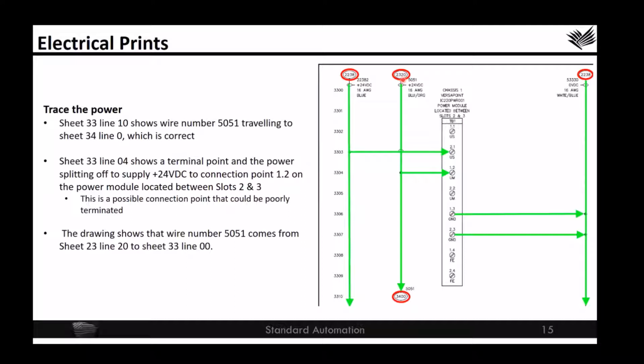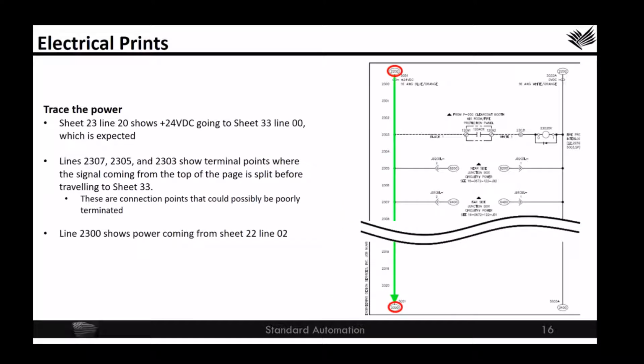If that checks out okay, then the drawing shows that wire 5051 now comes from sheet 23, line 20, and goes to sheet 33, line 0. Here we see on sheet 23, line 20, that the 24 volt power is going to sheet 33, line 0, as we expect. We can also see that there are three termination points, or terminal points, that the signal splits off to feed other devices. These are connection points that could possibly be poorly terminated. These are areas that, if you are having power supply issues, the power supply issue could be coming from these terminal points.